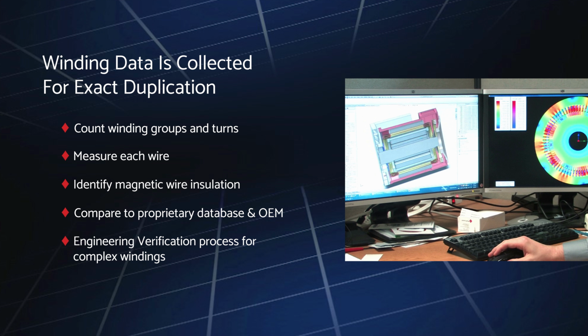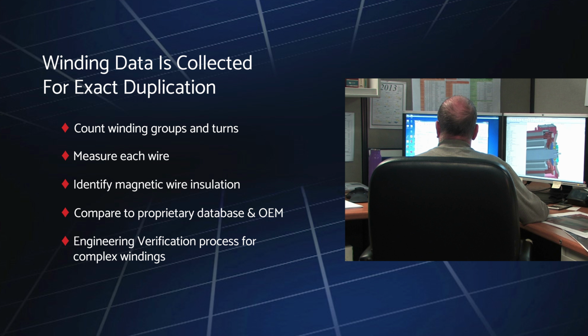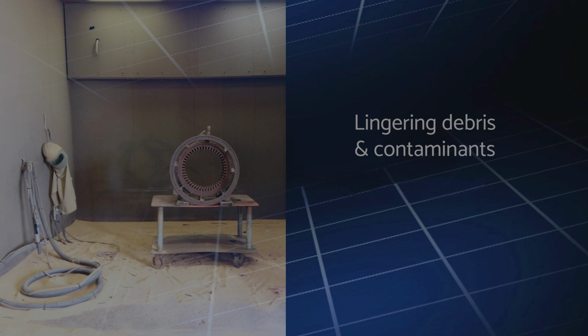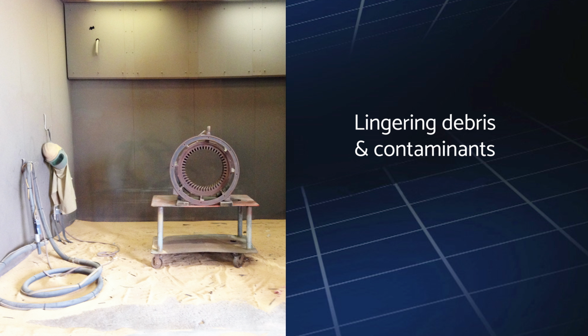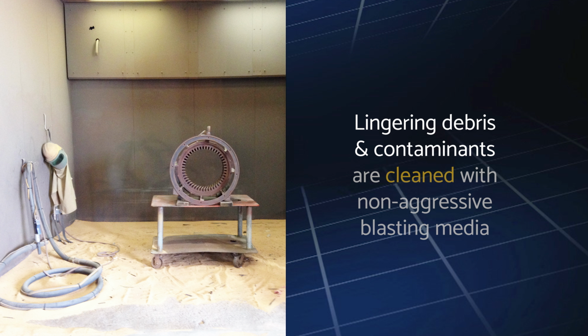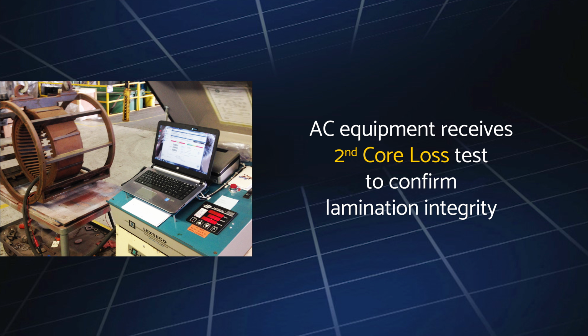Depending how complex the winding requirement is, we may also undertake a separate engineering verification process to ensure the highest level of winding precision. To remove any lingering debris and contaminant residue from the burnout process before the rewind begins, the stator is then thoroughly cleaned with non-aggressive blasting media. For AC equipment, we conduct another core loss test on the stator and compare it to pre-burnout results to confirm the integrity of the laminations.